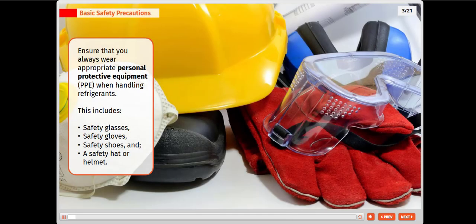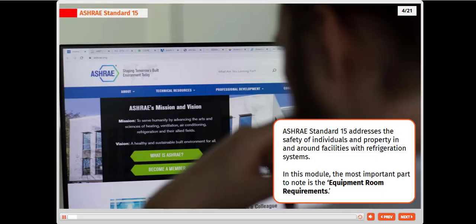Ensure that you always wear appropriate personal protective equipment when handling refrigerants. This includes safety glasses, safety gloves, safety shoes, and a safety hat or helmet. ASHRAE Standard 15 addresses the safety of individuals and property in and around facilities with refrigeration systems. In this module, the most important part to note is the equipment room requirements.